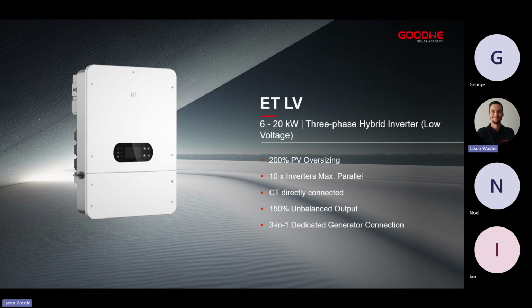Next feature, we'll touch on all of these as we go through, is the 150% unbalanced output, meaning that in off-grid operation or in backup mode, we can have an unbalanced output between the three phases of up to 150%. So what this means is if we have a 15 kilowatt inverter, for example, it's 5 kilowatts per phase if we break it down. Because we can do up to 150% unbalanced when in off-grid or backup mode, we can have 7.5 kilowatts on phase 1, 5 kilowatts in phase 2, 2.5 kilowatts in phase 3, and the system will be able to operate perfectly fine.